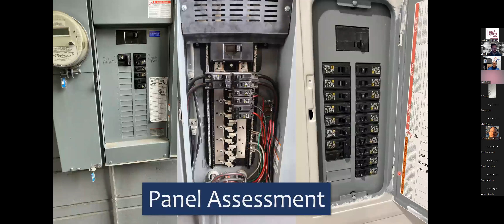Unfortunately, both sub panels were 100 amps each, and they were buried in the walls of the condos. The upstairs one was in the laundry room, on the wall in the middle of the condo, very difficult to run any circuits in and out of. So we ended up doing some creative stuff. The first solar guy that came and looked at it, and multiple other contractors, said you have a 100 amp panel here and it's almost full, there's nothing we can do, you're at capacity. We went out, looked at it, and did the actual calculation. These things were at 8,000 watts. The only 220 volt load was the dryer in each one, and it had a 100 amp wire going up to the space.